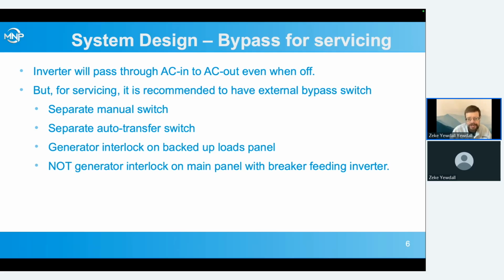Now, don't do a generator interlock setup like that on the main panel that has a sub breaker feeding the inverter. I've seen people do that, and it just doesn't work very well for many reasons. But one of the things that can happen is you can end up with the inverter output feeding back around into its own AC input. Then it thinks, oh, the grid came back, I don't need to be doing output. But then when it turns its output off, the grid stops, so it ends up all confused because it's feeding itself. So make sure that you don't have that kind of situation if you're using a transfer switch.